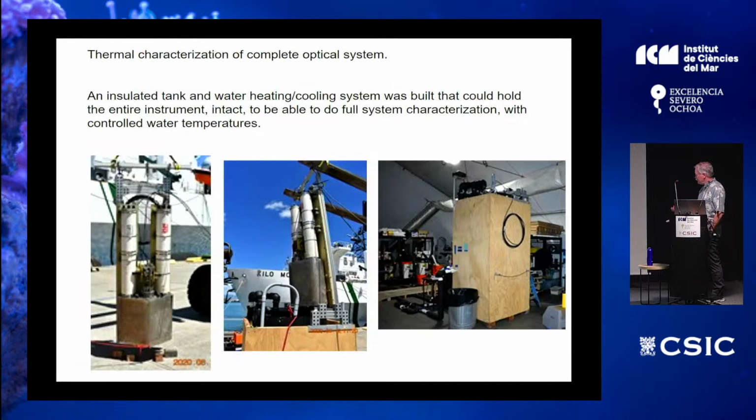We also have a nice little hot tub for the instrument to do thermal characterization. And this shows a prototype with PVC housing being dropped into it to be characterized.